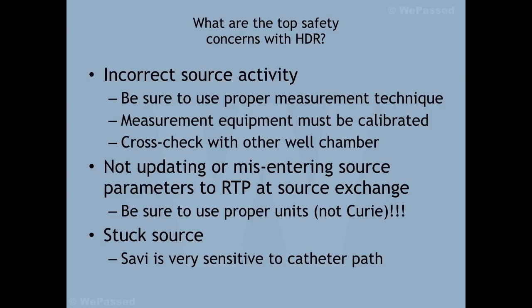So now for source activity you have three, maybe four things: one from your HDR console, a separate decay table, a decay table from your treatment planning system, and the data you measured. They should be consistent within 3%, but I like 1%. If it's too high, that's not good.